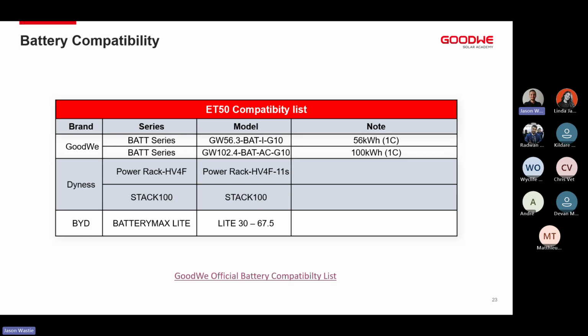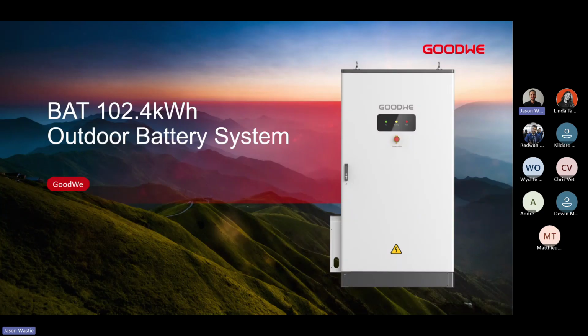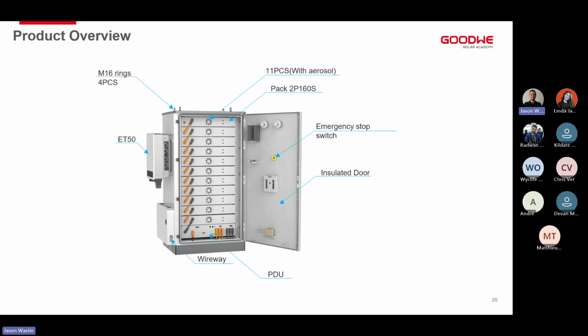So that's it for the inverter side of things. I'm just going to go through the two battery pairings that would go with the ET50 inverter from a GoodWe standpoint, the BAT 100 kilowatt hour battery and the BAT 56 kilowatt hour battery. So this is the BAT 102.4 kilowatt hour battery, or outdoor battery rack. This is an all-in-one battery cabinet. It weighs just over 1.3 tons, I think about 1.4, 1.5 tons, and it comes with everything already built in, as well as an additional external air conditioning unit on the back. So this is an all-in-one cabinet that we can use for our battery rack. The inverter gets mounted on the side of it, and your STS gets mounted closer to your main incomer.